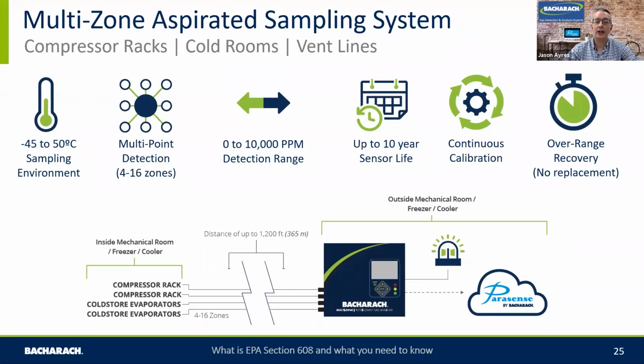It has a broad detection range, so we can detect down at those low level ppms. We can see leaks earlier, but we also have the ability to alarm at those higher ranges for safety compliance as well. So you can get safety compliance and low level leak detection in one solution. The technology in the solution is very low cost of maintenance, so the life cycle costs, like with any system, should be taken into account. The equipment, the technology, the sensor lasts for multiple years, so you're not having to replace systems on an annual basis. It gives you a very low cost of ownership. And with continuous calibration, it allows it to detect low level ppms. It keeps that sensor accurate and responsive to alarms.